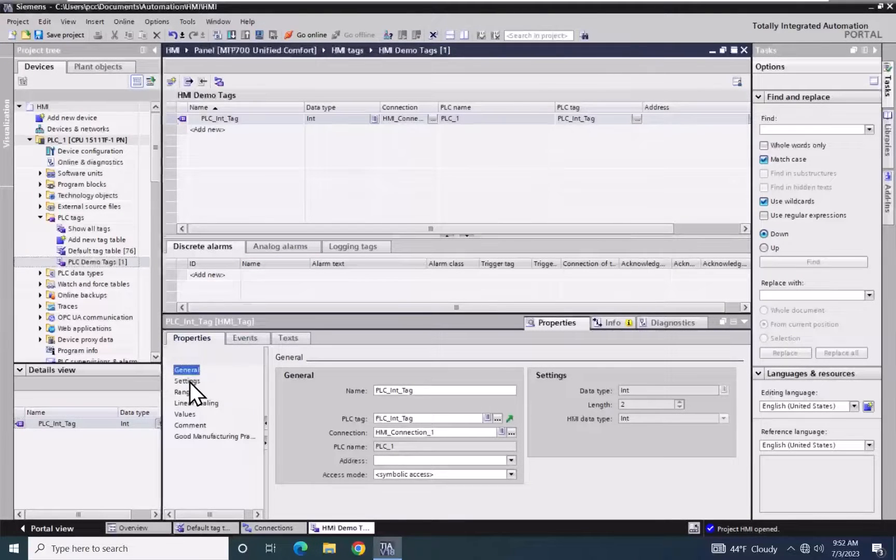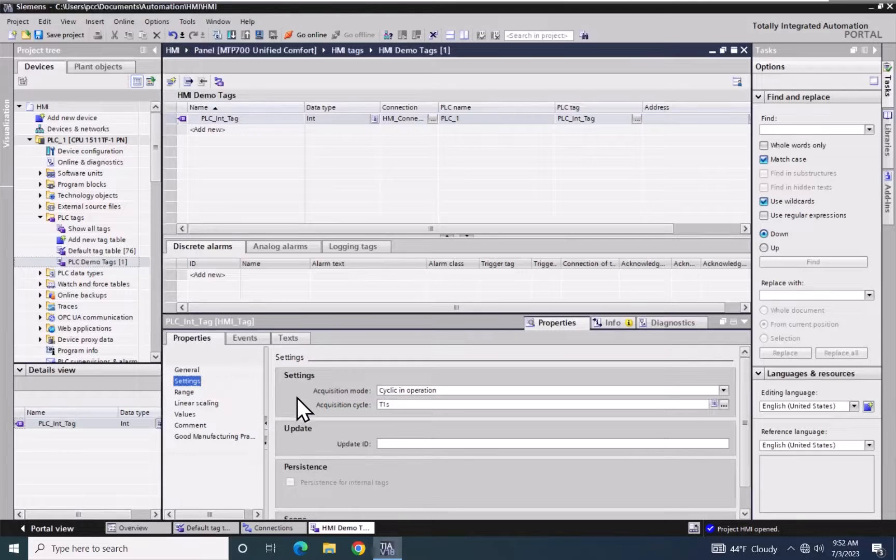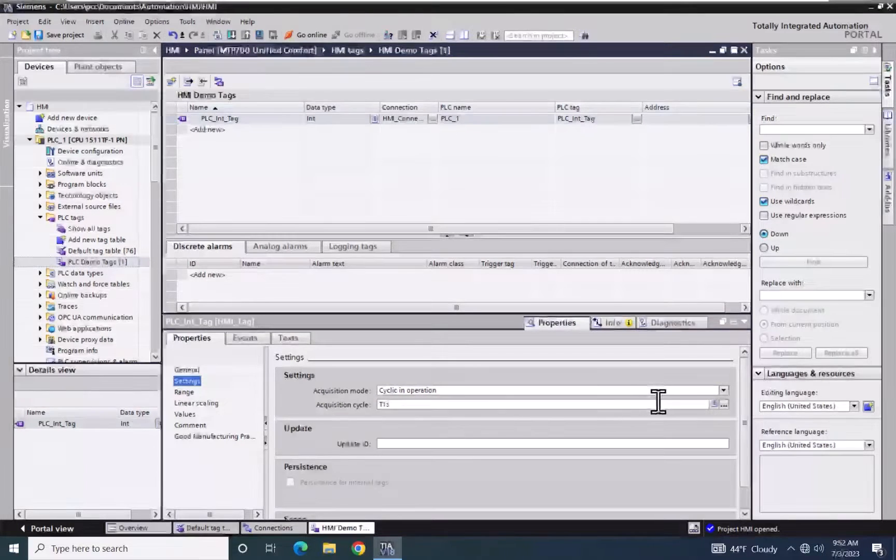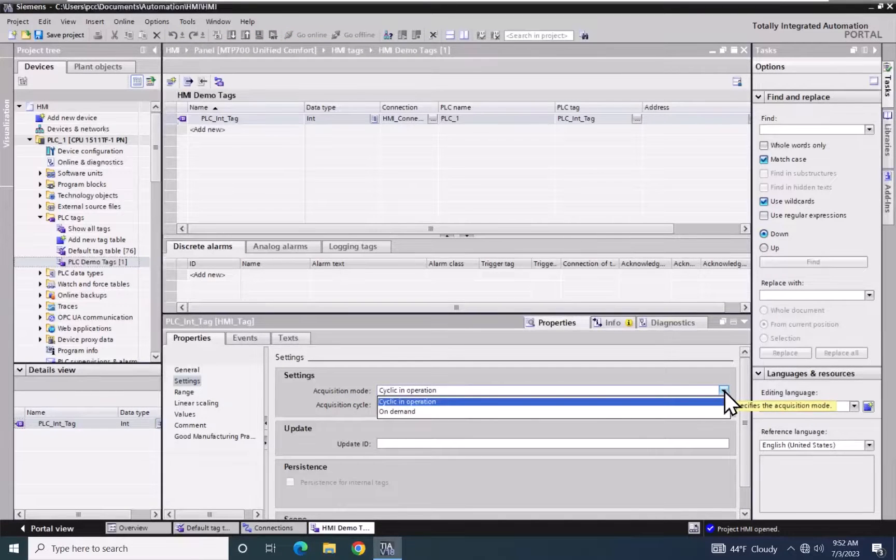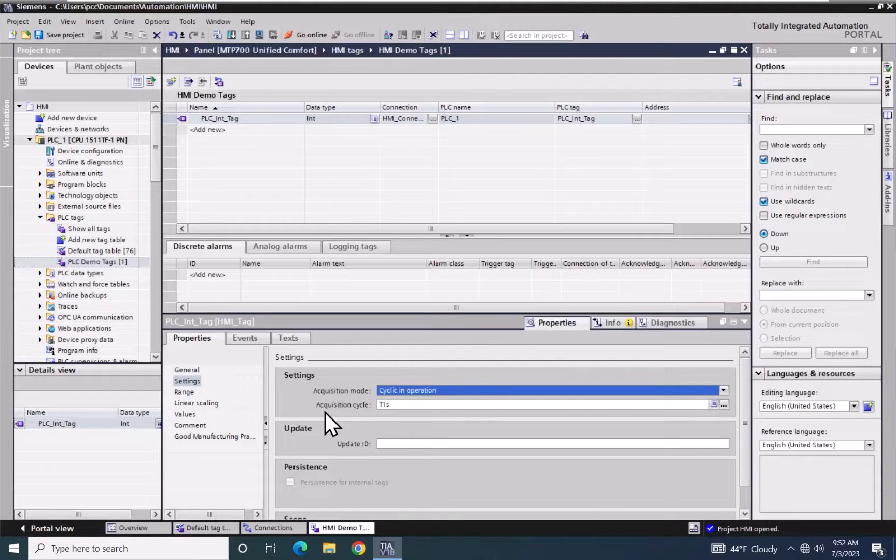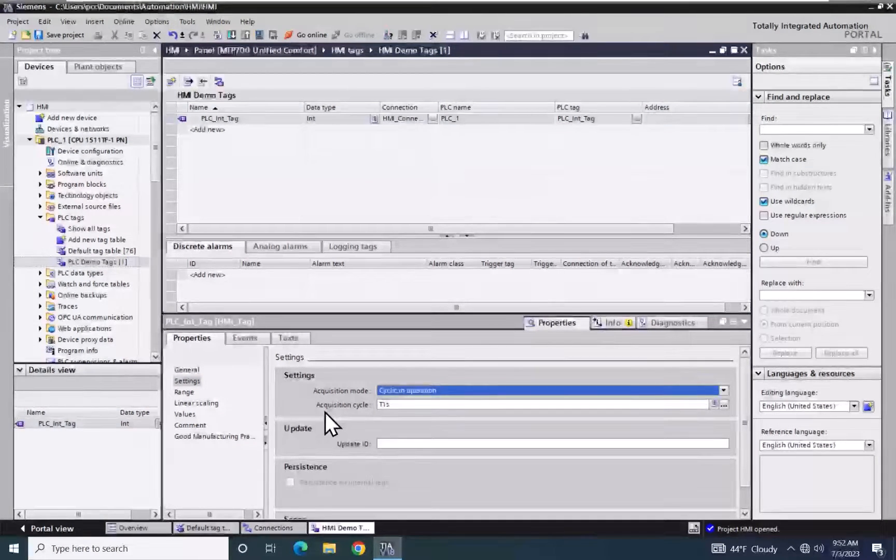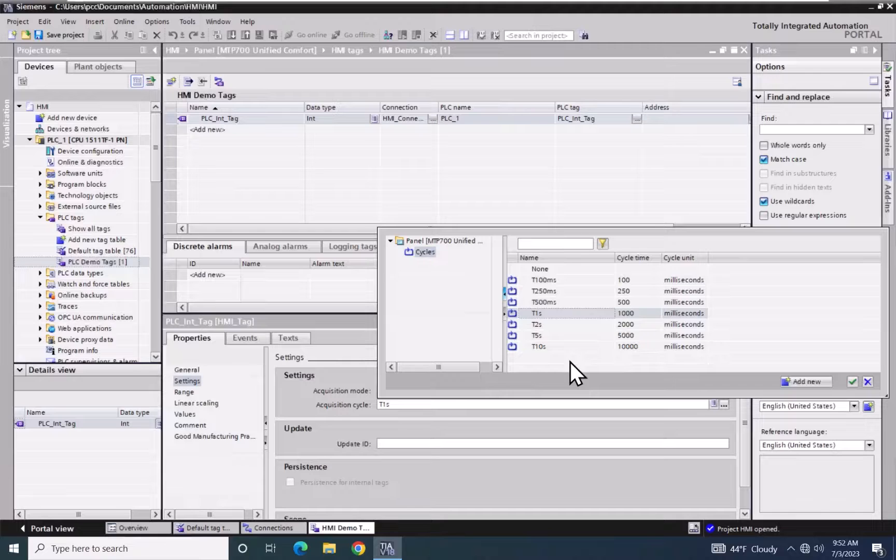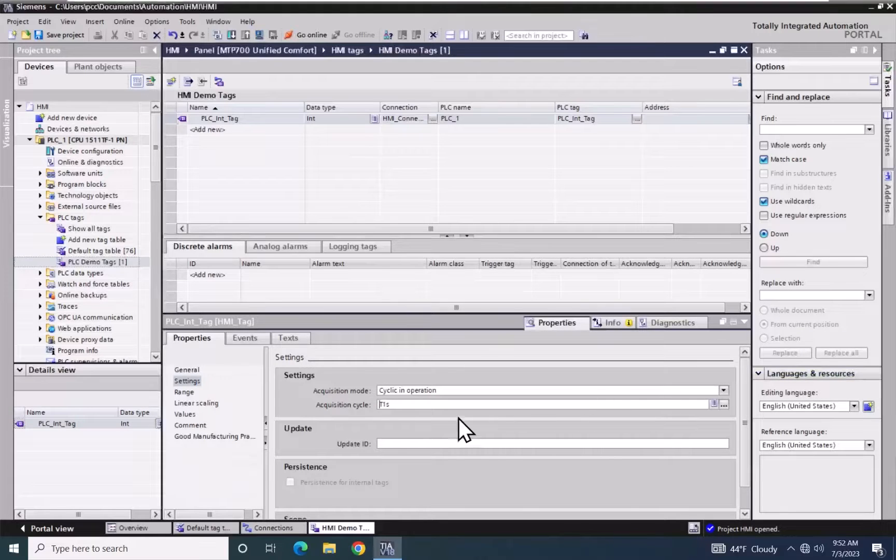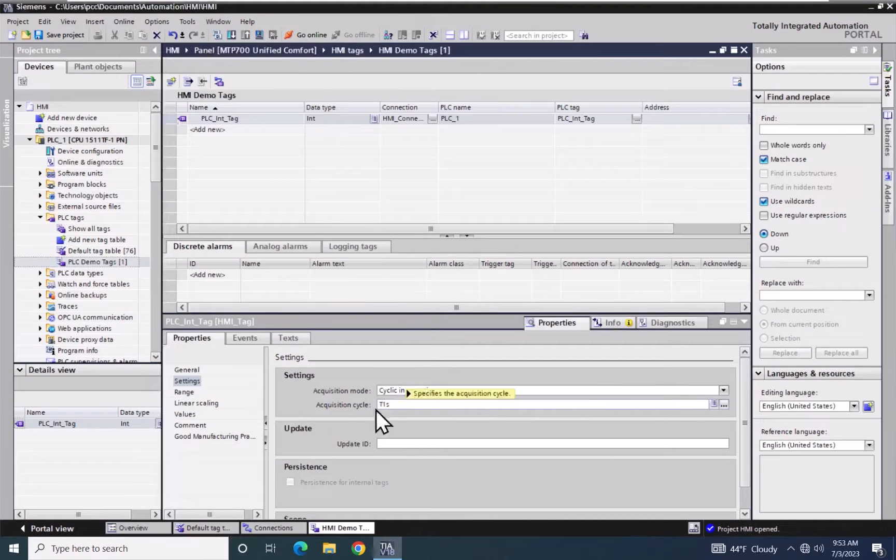I'm going to select Settings. Under Settings, the acquisition mode is cyclic in operation, and that's what you would typically use. The only other choice in Unified is On Demand. The acquisition cycle determines how fast this tag is going to be updated. I can select from one of the predefined cycles, or you do have the ability to create your own cycles at different intervals. So this tag would update on a one-second interval.